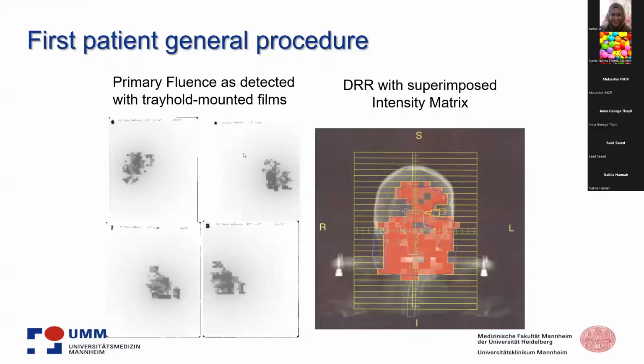You see it here. We put on the tray holder. We use tray holder mounted films to control that the machine delivered what the treatment planning system calculated. And this is a superimposed DRR with the intensity map. So we want to have an idea what gets delivered. Is there something missing in these things?